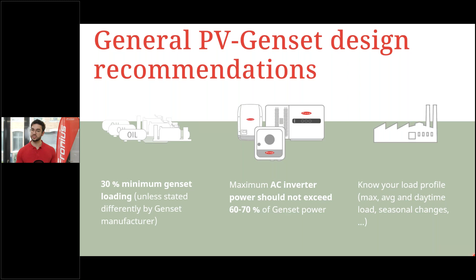Vice versa, of course, we need to also make sure that the maximum AC inverter power should not exceed 60 to 70% of the genset power. And of course, like in every system, know your load profile. Make sure that you have an annual overview of what's going on, what's the maximum, the minimum load, what's the average and daytime load, for example. Is there a seasonal change that you can account for? And then after you know that, then you can design a little bit better the size of inverter and genset solution. All right, that's the first topic.